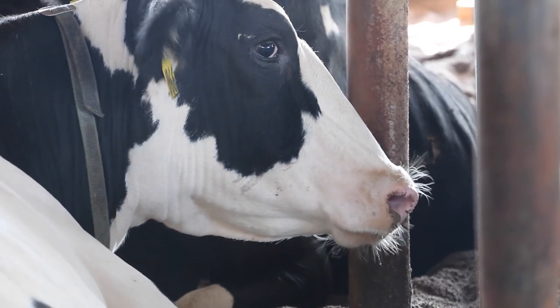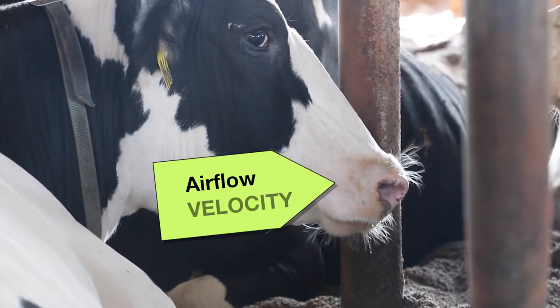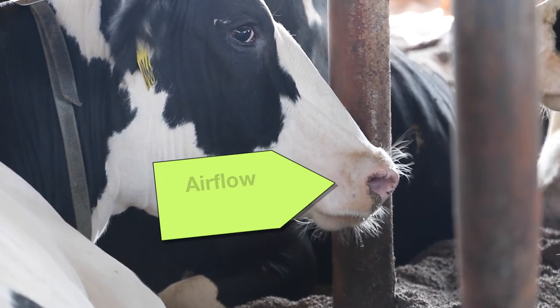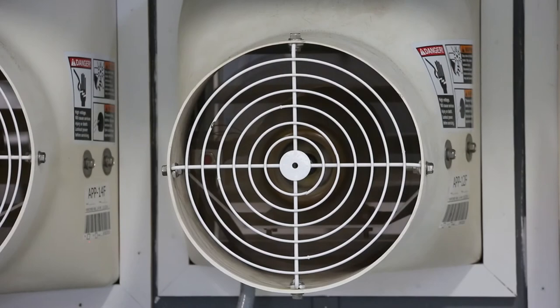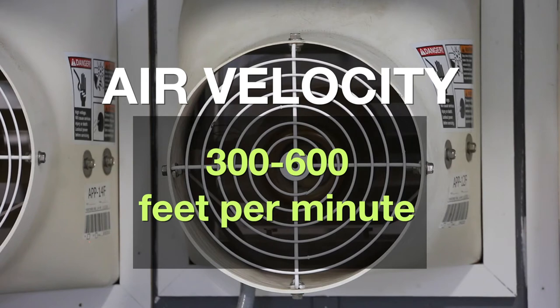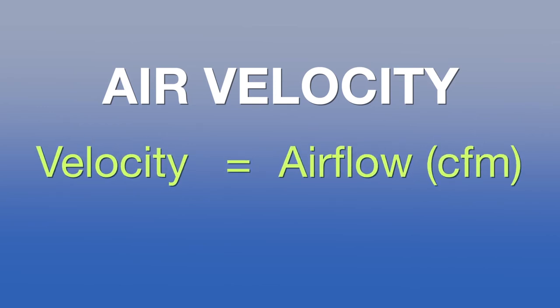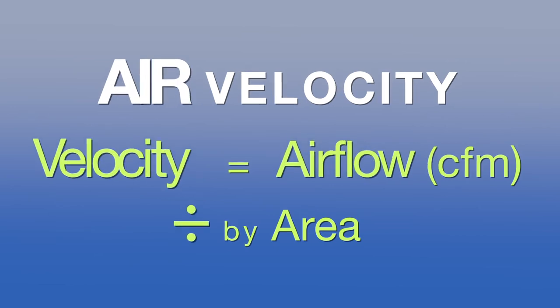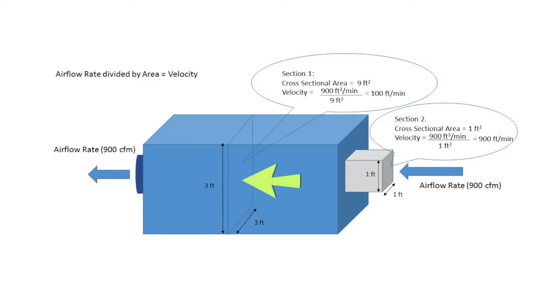These systems can also be designed to increase the velocity of air moving past the animals to help remove body heat. Air velocities from 300 to 600 feet per minute are used to enhance evaporative cooling. Air velocity can be calculated with this simple equation: velocity equals air flow, or CFM (cubic feet per minute), divided by the area. The area is the cross-sectional area of the barn in the path of the airflow.